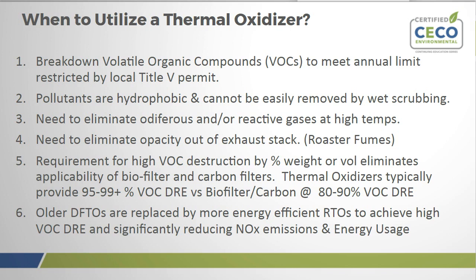If you have odors or reactive gases, you're going to need a thermal oxidizer at higher temperatures there. A lot of times you'll see roaster fumes from coffee roasters and things like that have applied thermal oxidizers through the years, actually afterburners, to take care of the fumes and smoke. But there's a lot of odoriferous compounds you'll see in food processing, rendering, fragrance, and perfume type manufacturing applications. There are VOCs and solvents in there, and there are some longer chain hydrocarbons on that. The requirement for the high VOC destruction is typically done percentage by weight or volume. And the higher VOC destruction efficiencies in most cases eliminate on a practical basis the use of biofilters across the board or carbon filters. Carbon filters have to be replaced and rejuvenated.